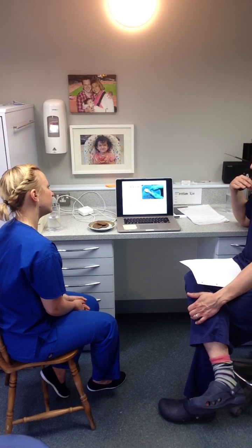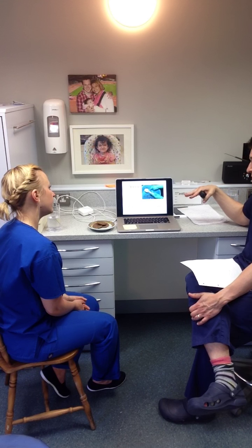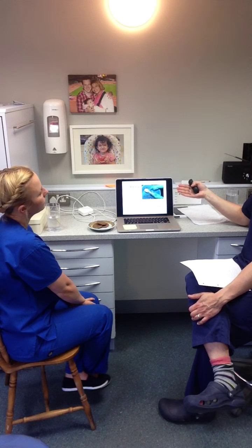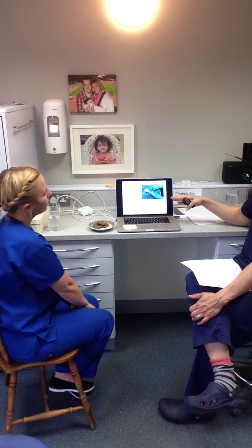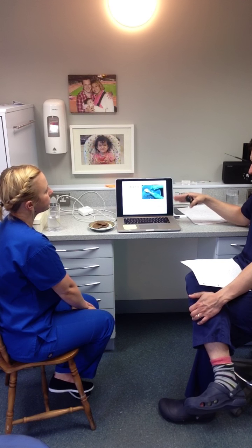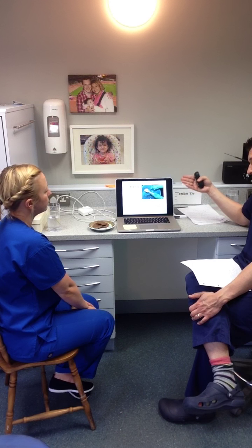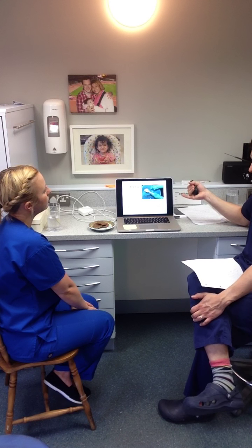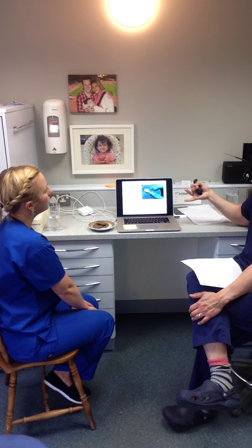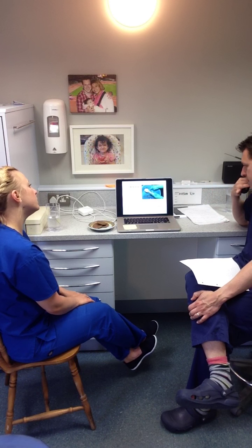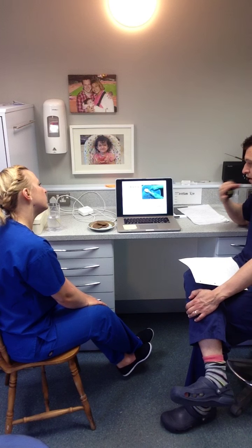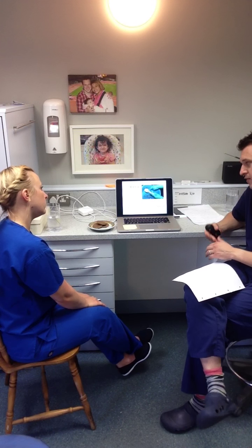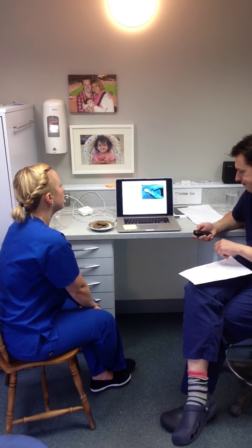So if you are setting up a new decontamination facility or moving to new premises, HTM 01-05 would want you to eradicate manual cleaning completely and use a washer disinfector instead. We don't use a washer disinfector at the minute. Number one, because it's not mandatory, but also we just don't have enough instruments to do it. It's something we would look at in the future. Should legislation change to say that we need to use a washer disinfector, then of course we'll do it.